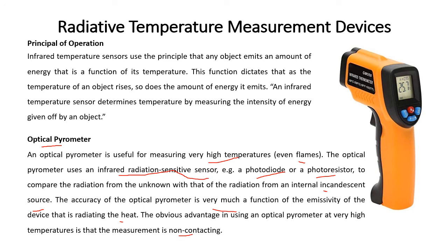So these pyrometers are basically working under the principle that every body emits radiations, and these devices are capable enough to measure the radiation coming out of these hot bodies, and they correlate this intensity of emission to a corresponding temperature which gets displayed on the screen, and you get to know the temperature. So you can also use these radiative temperature measurements against RTDs and thermocouples to do a cross check of whether your RTDs and thermocouples are working perfectly or not.